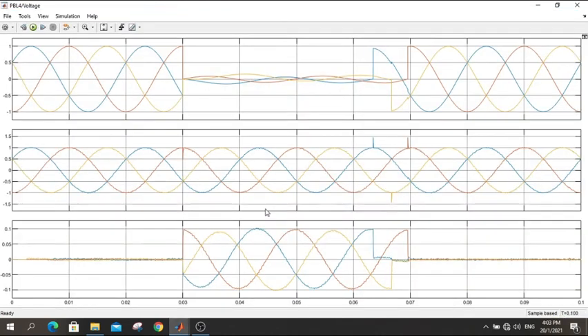This is the result after we use the DVR system as a mitigation technique, and it shows the voltage sag at 0.03 to 0.06 seconds has been fixed and no voltage sag occurred at this time. Therefore, the output voltage for the phase to ground fault has been improved and has a constant value of voltage.